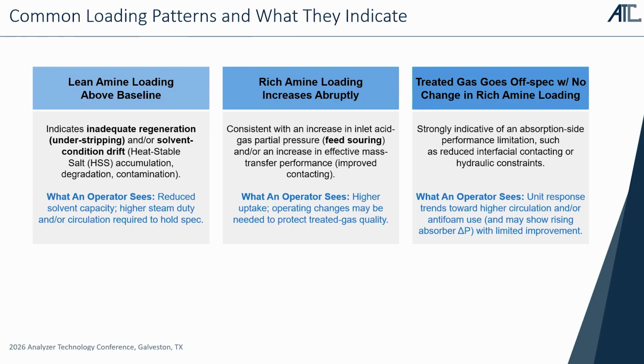I know it's a little text heavy, but some common loading patterns and what they indicate, from what our customers tell us when we go on site with them: when their lean amine loading is above baseline, what the operator actually sees is reduced solvent capacity, higher steam duty or circulation required to hold that spec, which is just wasted energy and wasted money. Sometimes operationally they'll see their rich amine loading increase abruptly, so it'll just spike out of nowhere. Their feed could get soured, and what an operator sees at that point, that lets them identify that that's a problem, is higher uptake in the amines, and operating changes need to happen to protect the treated gas quality. So again, they're just trying to get themselves back on spec.